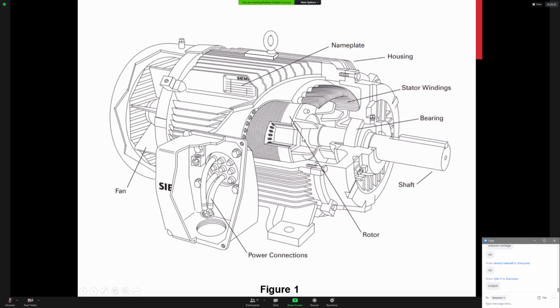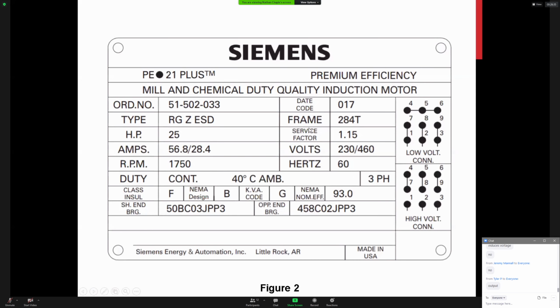through the stator, the rotor, we enter in the nominal system voltage and current, so the FLA of the motor. And the variable frequency drive will do some calculations and determine what this overload setting should be in order to protect the windings inside the motor and also protect the branch circuit conductors, because the overload protection does both.